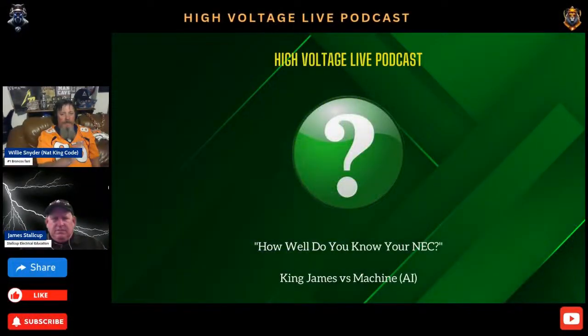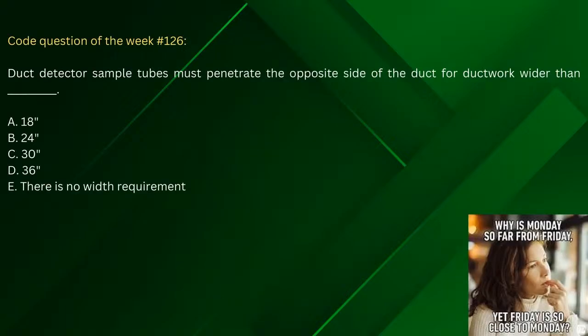I don't have a worry if you get this right, I think this is like a softball for you, but I went outside the National Electric Code, outside NFPA 70, into NFPA 72, though I think this relates to NFPA 70 a little bit too. We'll see what you think. Duct detector, is this for fire alarm? Yeah, you have duct detectors, and basically it's drilled out EMT that you put into the ducts. They're not really required to be supported, they can dangle a little, but there's a certain dimension where they have to penetrate the other side of the ductwork.